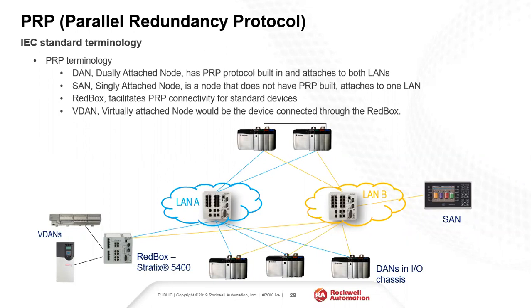But if you're thinking of just, I need a simple network and I'm okay running a ring, my device level ring, because of the fact that I can minimize the number of switches and I can tie in and do a daisy chain and I can mix and match between fiber or copper connections, it's usually an easier benefit on me. And up to 50 devices, I can qualify you at that 3 milliseconds time. And the 50 devices isn't really a hard limit, but that's kind of where we test it to keep within bounds of that 3 milliseconds.